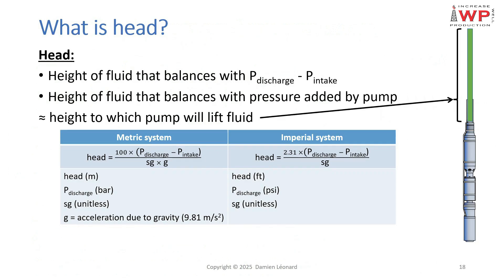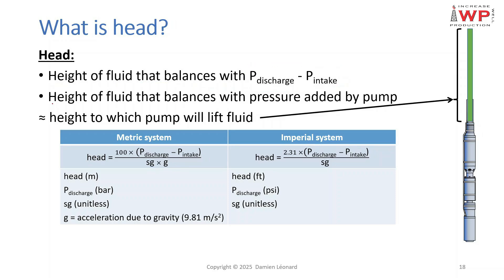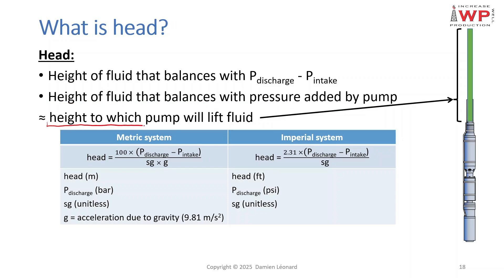The most important curve shows head versus flow rates. Head corresponds to the height of fluid that balances the difference between the pump discharge pressure and the pump intake pressure — in other words, the height of fluid that balances the pressure added by the pump to the fluid, which is approximately the height to which the pump will lift the fluid.